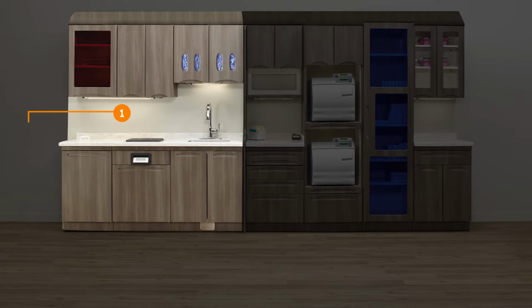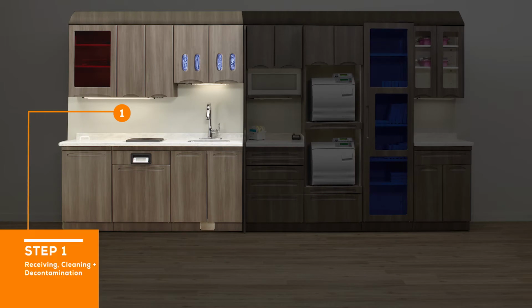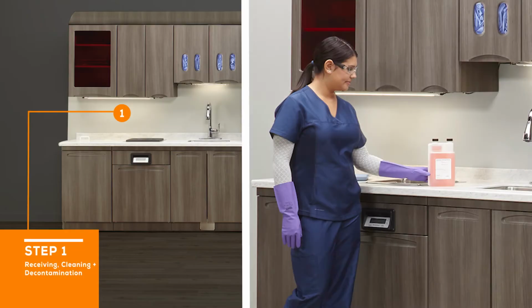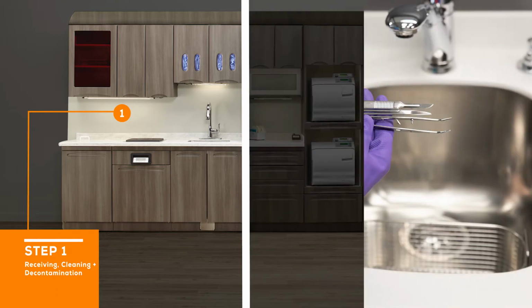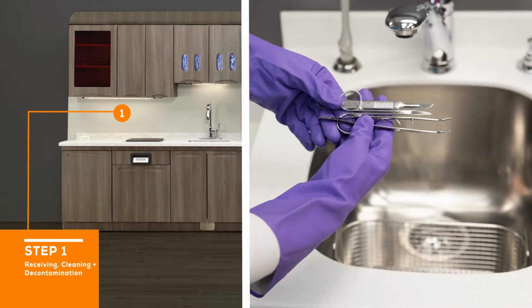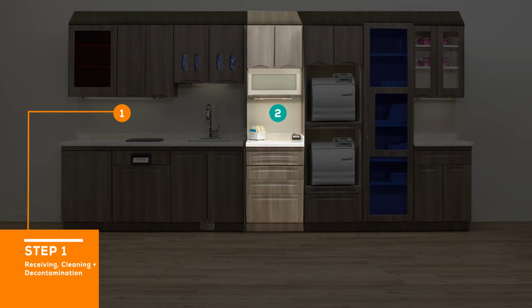Step 1. Receiving, cleaning, and decontamination. Reusable instruments, supplies, and equipment should be received, cleaned, and decontaminated in one section of the processing area. It's important to ensure that all instruments, supplies, and equipment are thoroughly cleaned of organic debris prior to sterilization, or sterilization will be ineffective.